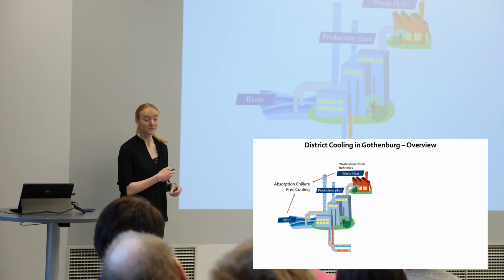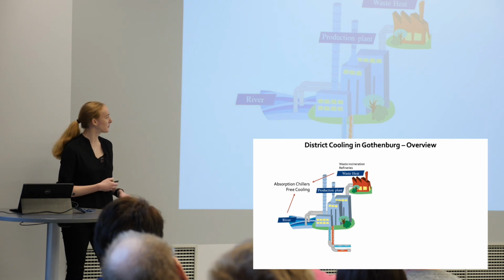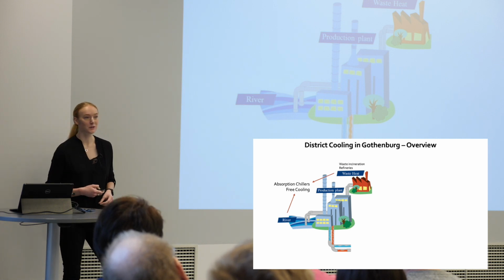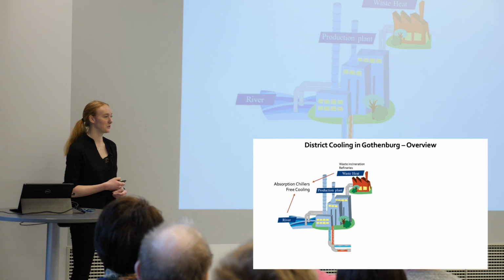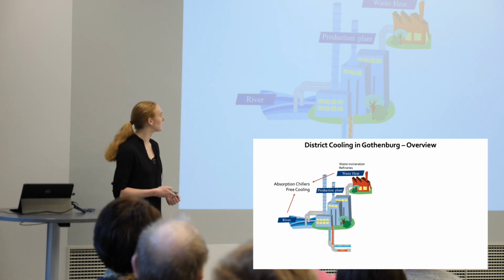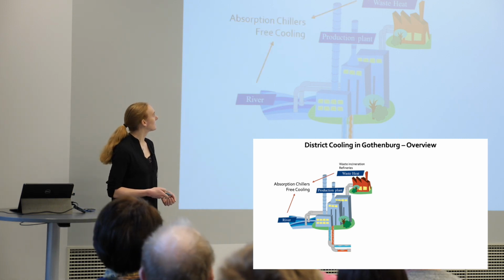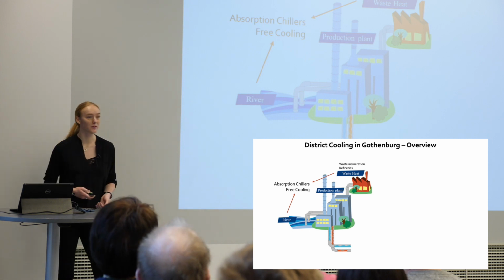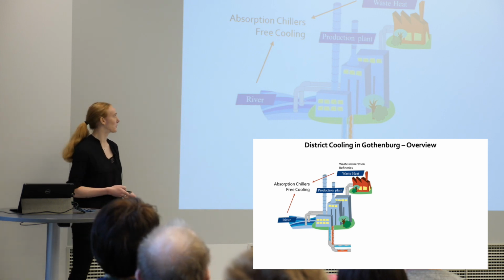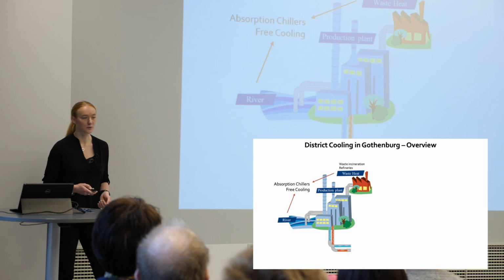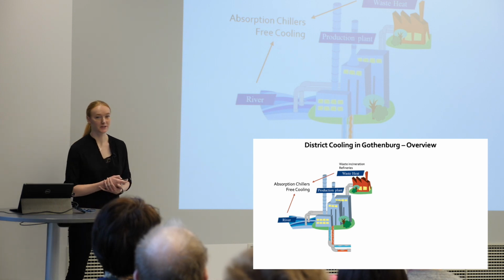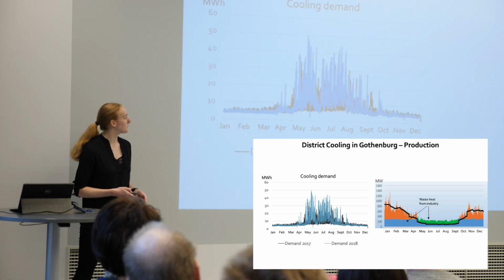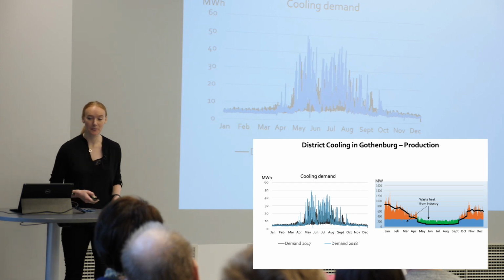And also there's a river in Gothenburg, and that river is used for free cooling when the temperature of the river allows. So the waste heat is good for absorption chillers, and the river is good for free cooling. And then of course we also have electric chillers for backup and peak production.